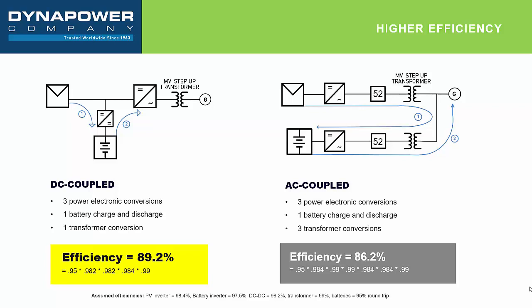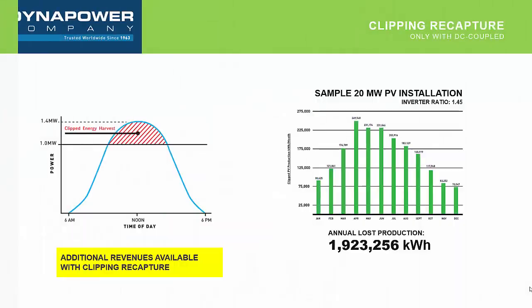Now you can take a look at the assumptions here on this slide for all the conversion efficiencies. The net result, though, is that you have up to a 3% efficiency advantage in the round trip when comparing DC coupled to AC coupled. This obviously translates directly into kilowatt hours for the developer and dollars saved across the system. So now let's shift more directly to the revenue side.